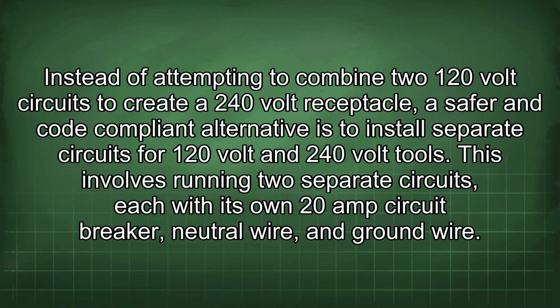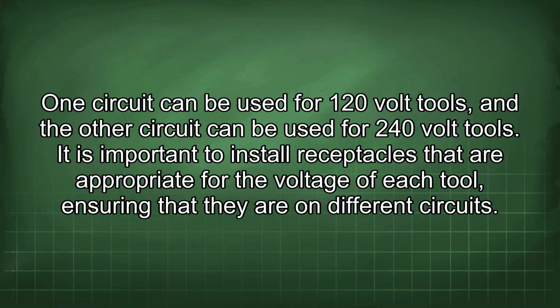Instead of attempting to combine two 120-volt circuits to create a 240-volt receptacle, a safer and code-compliant alternative is to install separate circuits for 120-volt and 240-volt tools. This involves running two separate circuits, each with its own 20-amp circuit breaker, neutral wire, and ground wire. One circuit can be used for 120-volt tools, and the other circuit can be used for 240-volt tools. It is important to install receptacles that are appropriate for the voltage of each tool, ensuring that they are on different circuits.